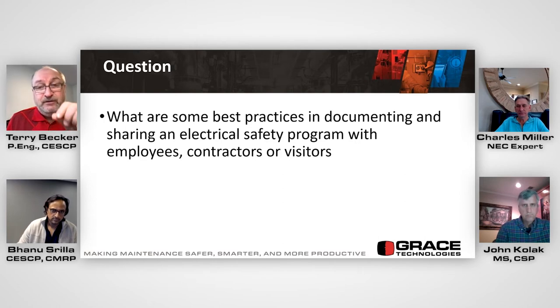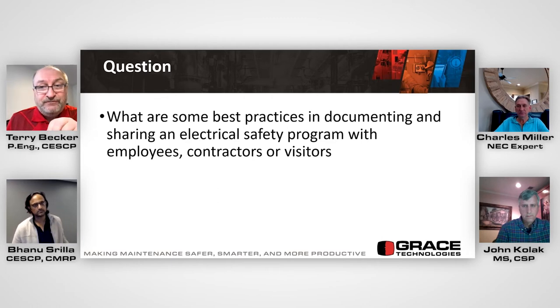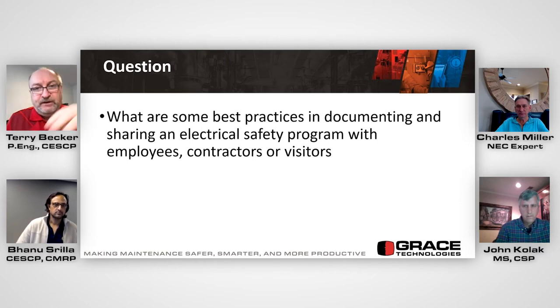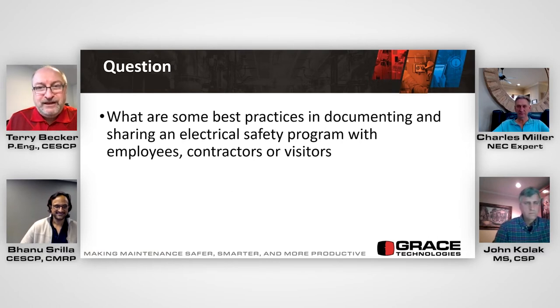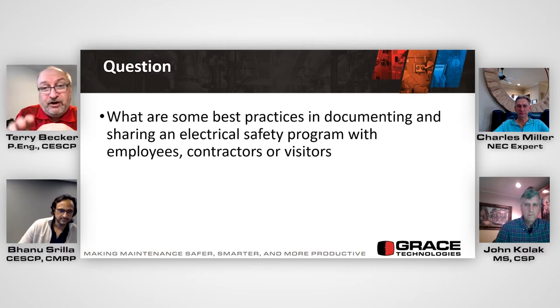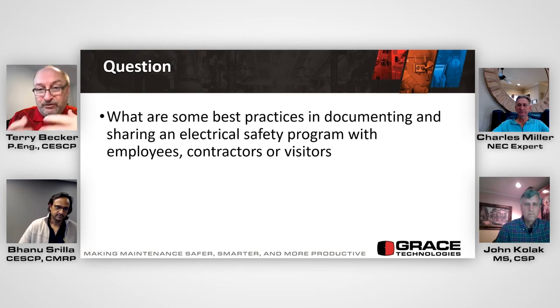I'm now telling you my exact policies, practices, and generic procedural requirements that you shall follow, right, that will meet or exceed 70E or Z462. And that's what's missing. Oh, they went on 70E, they're just going to do that. No. You want to have your own electrical safety program and tell them you're going to apply that generic training against our electrical safety program to make sure you eliminate exposure or reduce your personal risk to as low as reasonably practicable. So again, you need to communicate your own policies and practices. Don't rely on the training to establish them.